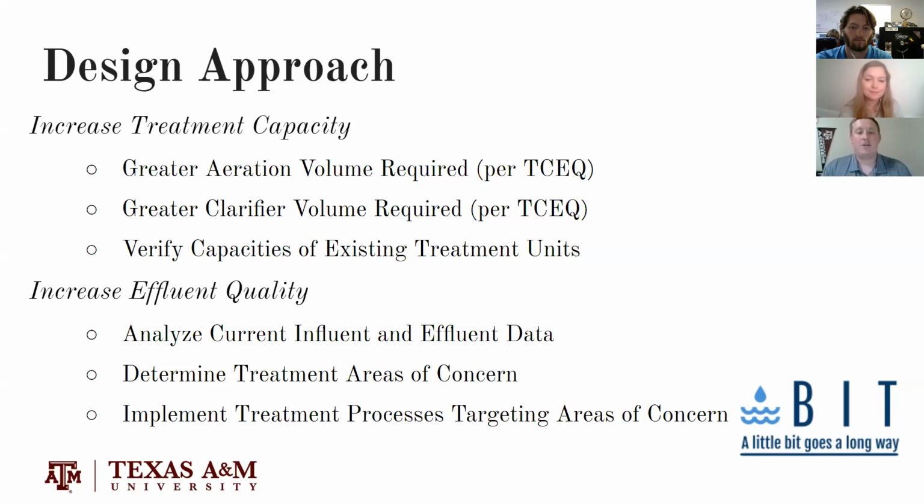Lastly, we wanted to take a look at the existing treatment units and verify their capacities based on the most recent influent and effluent data to determine if these basins were being used as best as they could, or if there was any way we could modify them to squeeze a little bit more capacity out of them.